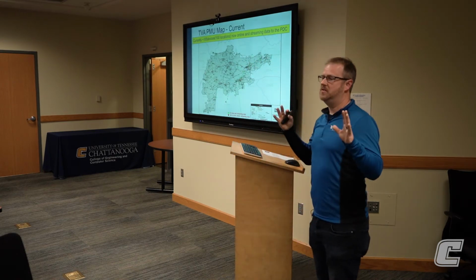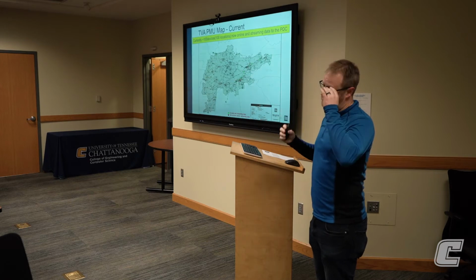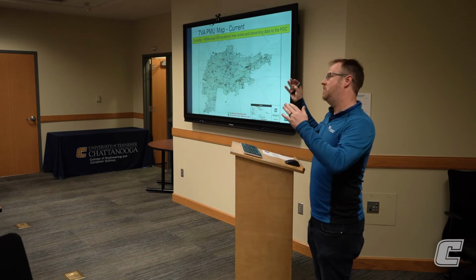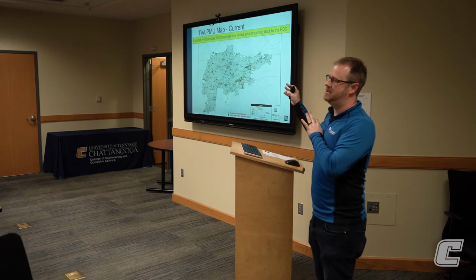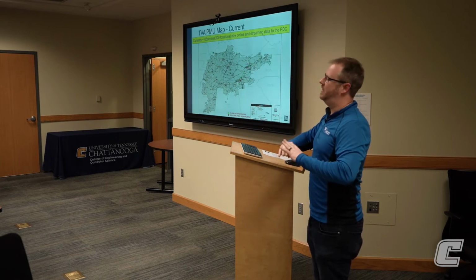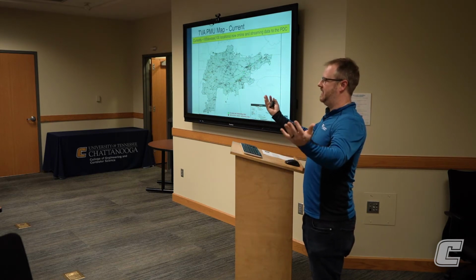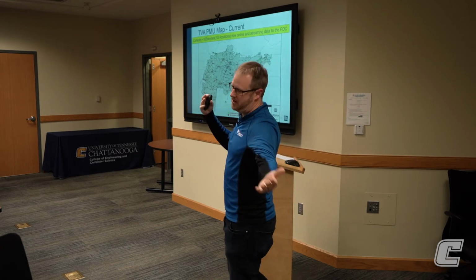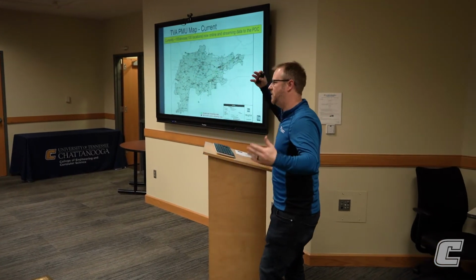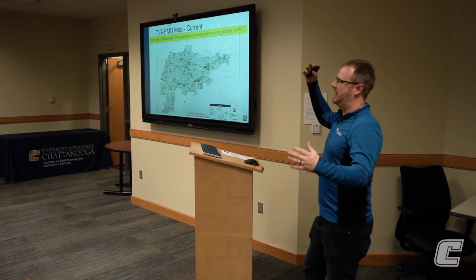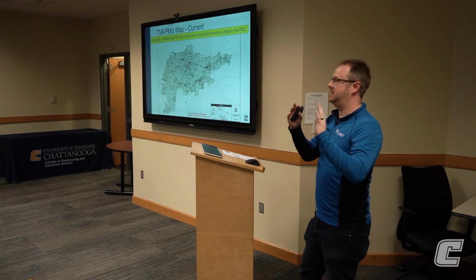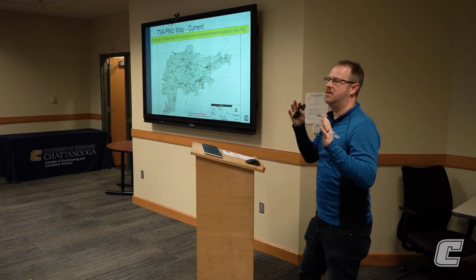You have to have a big server somewhere. We have several big servers downtown, and that's what they do. Remember I showed you that we had the PDC, phasor data concentrator. All it is, is a big server, and it takes all the PMU data from Johnson City over to Memphis, to Starkville, to Bowling Green, and it time aligns everything because it's got a timestamp for every value that comes into TVA.